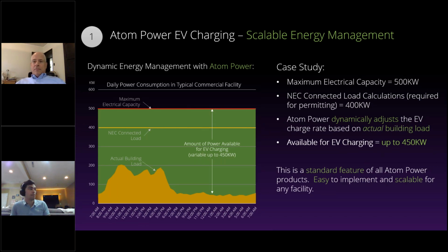When you have a connected load in your building, you've got an HVAC system, lights, equipment, and all of that load has a full load rating. When you do an energy audit, you look at all those loads, add them up, and give them a usage factor, since they might only run a certain percentage of the time. But that doesn't mean they're always running at that percentage, they might all run at the same time for part of the day.